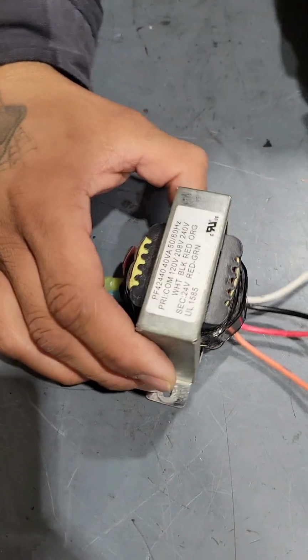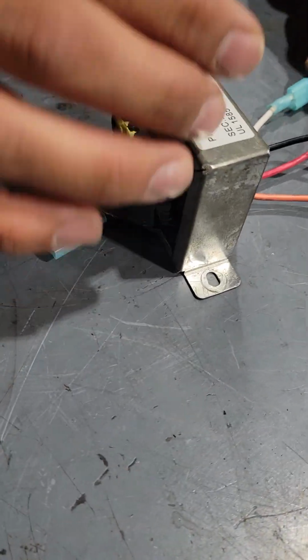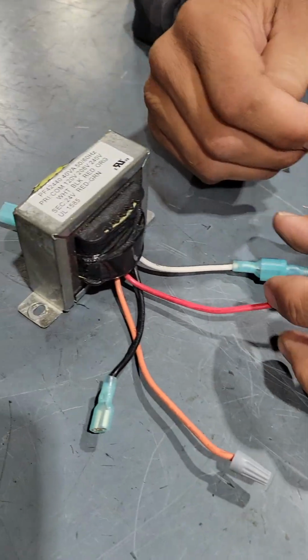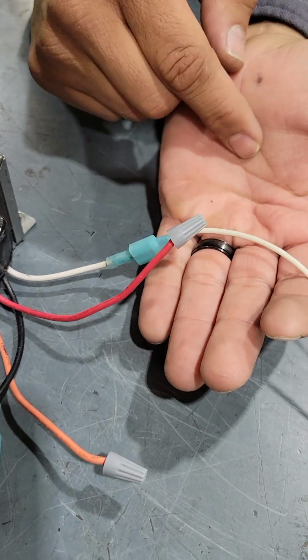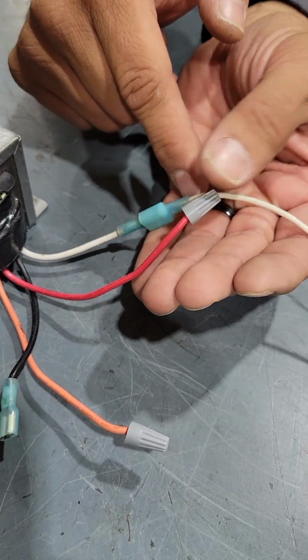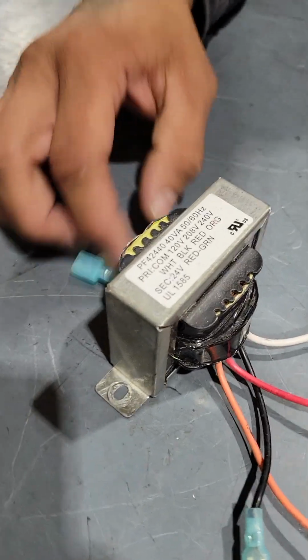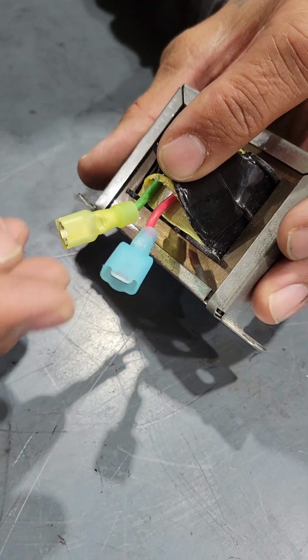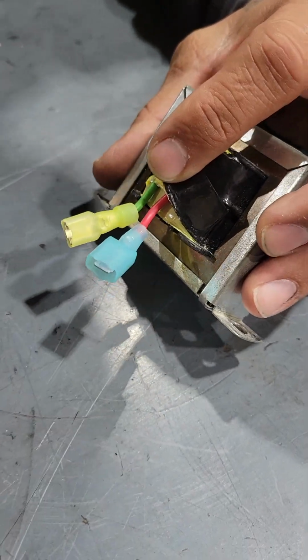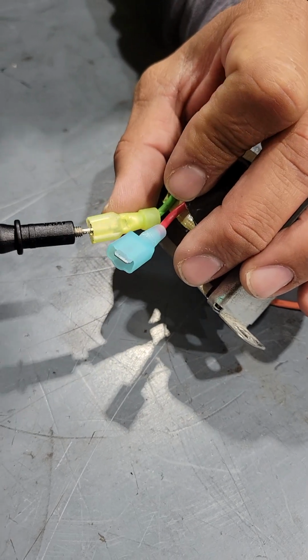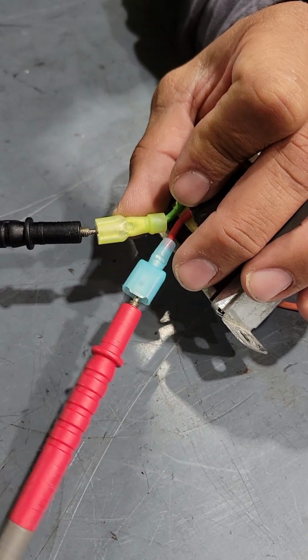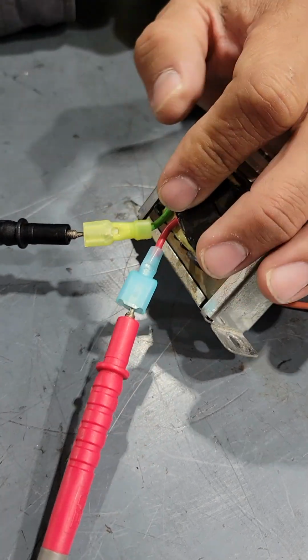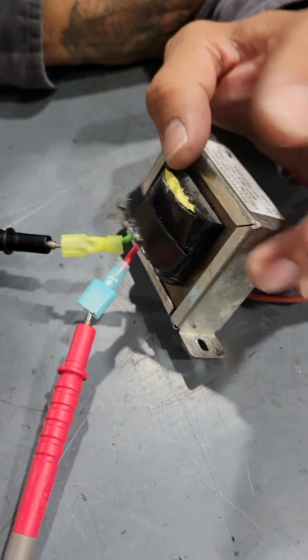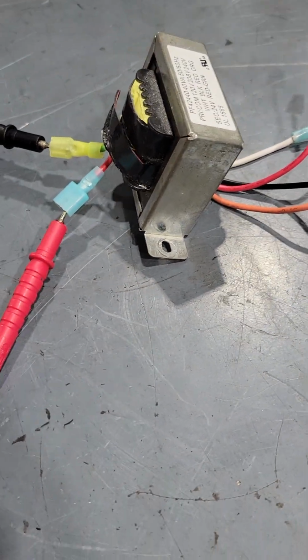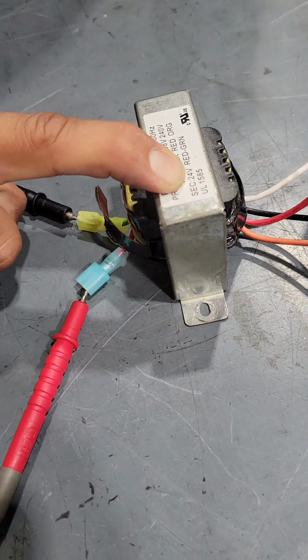To troubleshoot this guy, real simple. We're going to use the same voltage we have here in the shop, 208 volts. That's what is wired to our unit, 208 volts, okay? Our secondary side, between the red and the green wire, which are right there, should be measuring 24 volts. So this isn't going to measure anything because it's off, but let's say you put your leads there and your meter is reading 8 volts. Hell, let's say even 12 volts, okay? We know that that is nowhere near enough of what we should have.